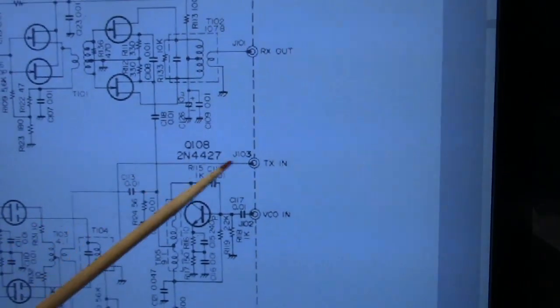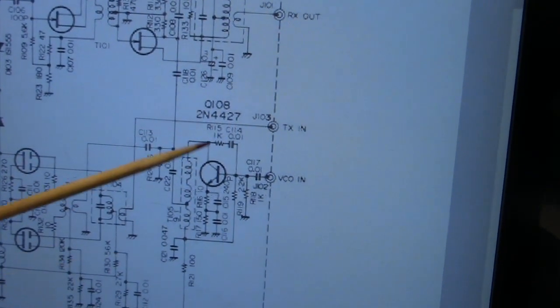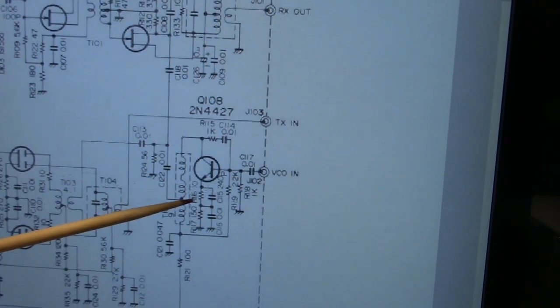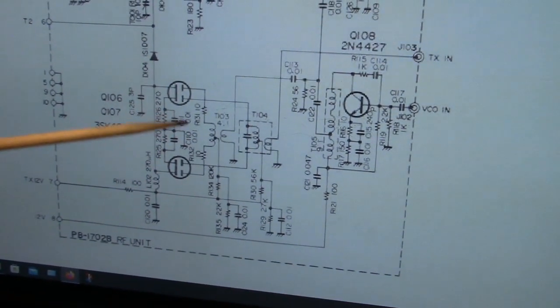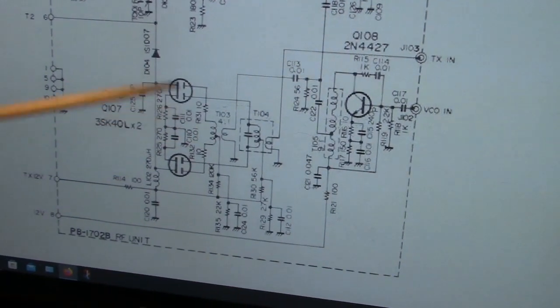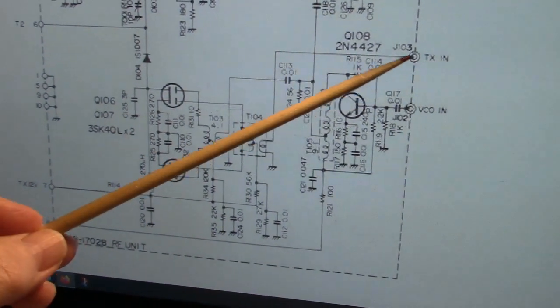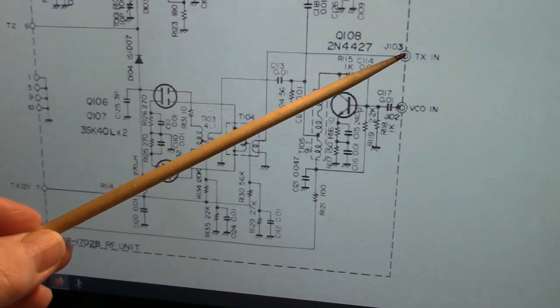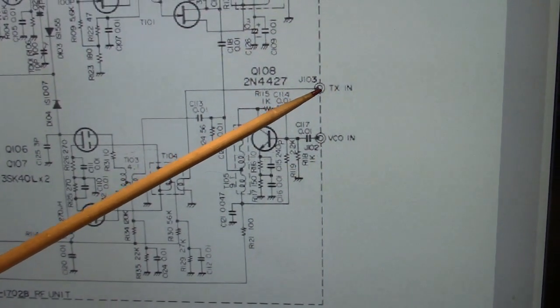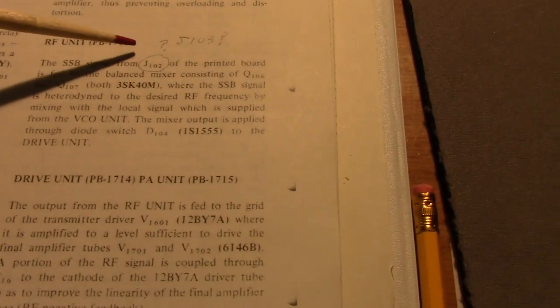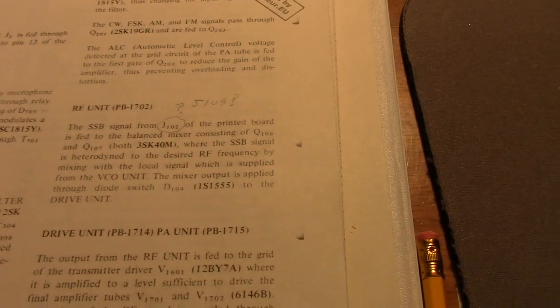If you look on the schematic, here it is, J103. J102 is a VCO in, this feeds an amplifier here, a buffer that feeds the balanced mixer. This heterodynes the signal up to the output frequency through this balanced mixer here. So the transmit, which is the red shielded cable, comes in on J103, not J102, as it says in the manual.